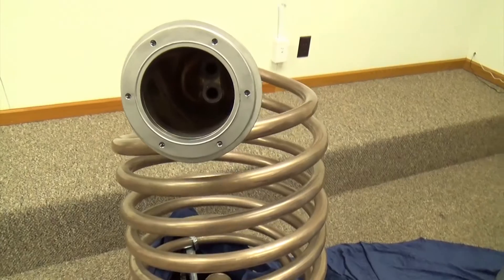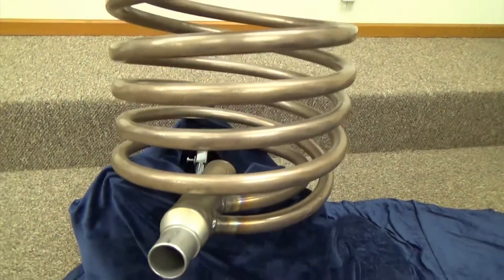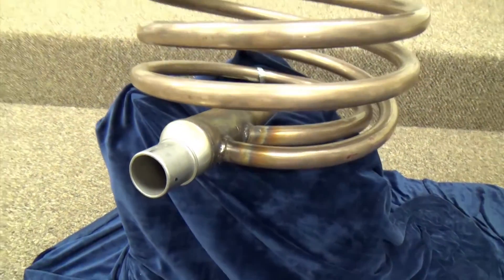To start, let's take a look at the heart of the Phoenix LD. The heart of the Phoenix LD is the Spiral Design Copper Nickel Heat Exchanger. The spiral design accommodates the rapidly changing temperature and allows the coil to flex. That flexing prevents scale and mineral from depositing on the coil, meaning better heat transfer over a longer period of time.